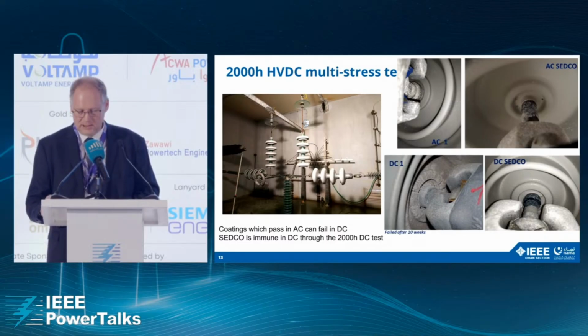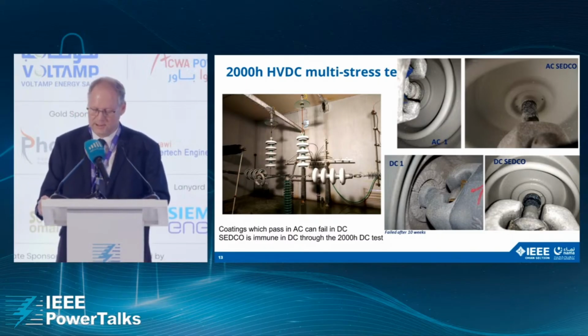As you can see in AC condition, the two coatings do not show any erosion and pass the test. However, when you make the same test in DC condition, coating 1 shows significant erosion and does not pass the test, whereas SEDCO coating is in good condition. So this demonstrates that the 2,000-hour multi-stress test is also effective in discriminating coatings when used in DC conditions. And coating quality required for DC application shall be much higher than the one required for AC application.